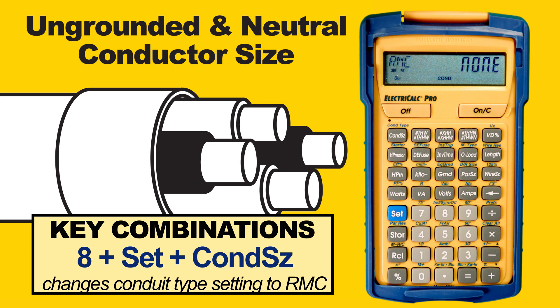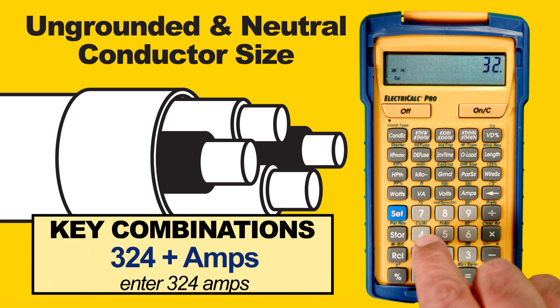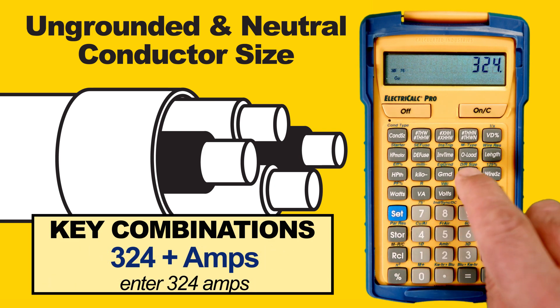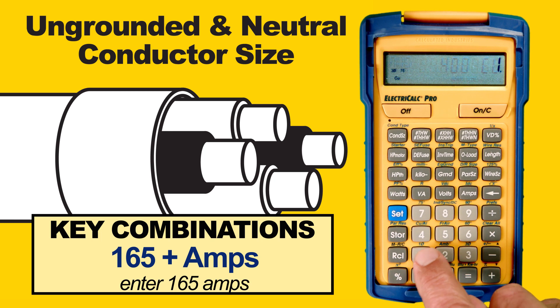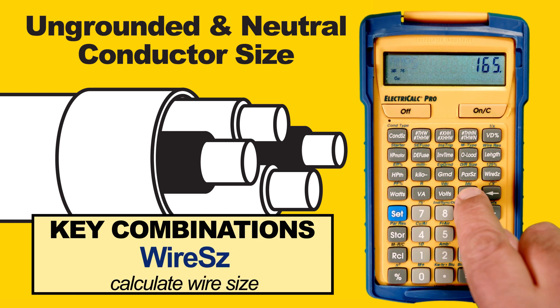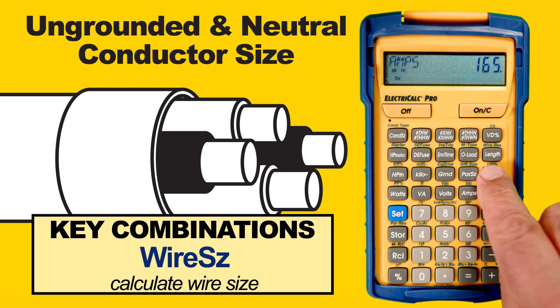Now we just need to re-enter the ungrounded feeder ampacity that we calculated previously as 324 amps. We enter 324, press Amps, then press Wire Size. We get 400 kcmil copper wire size. The final step is to enter the neutral conductor ampacity, which we calculated at 165 amps. We enter 165, press Amps, then press Wire Size, and we get the 2-0 wire size, as the book does.